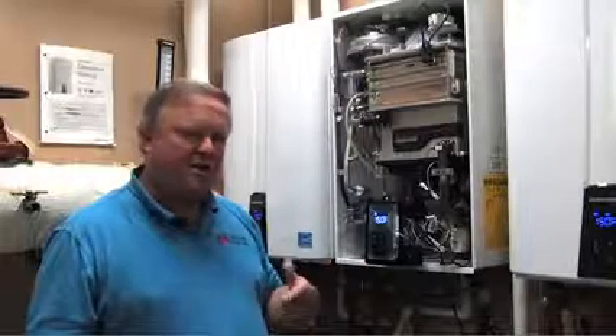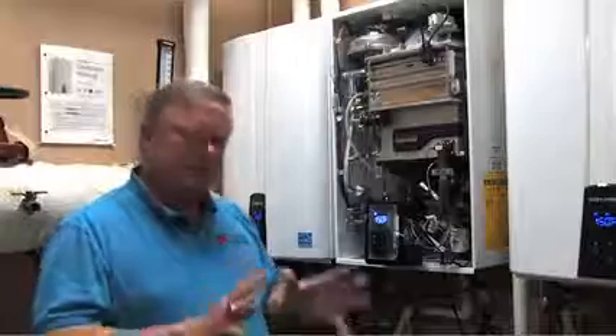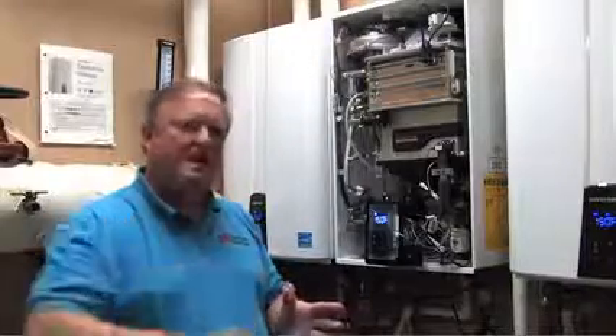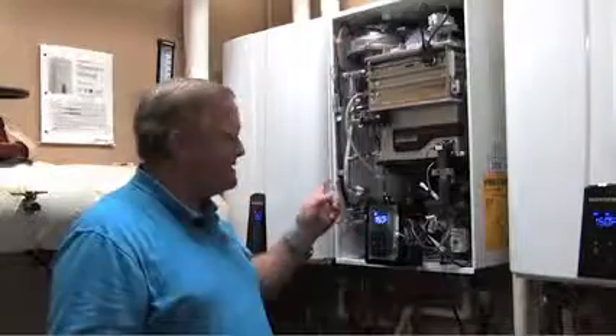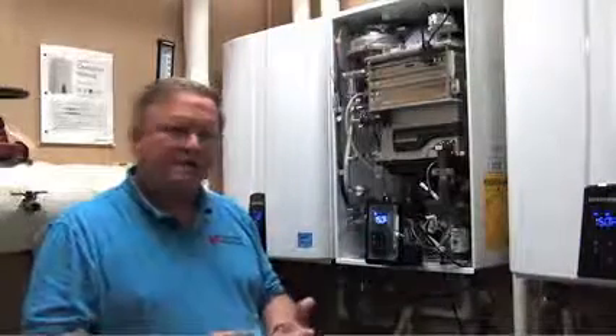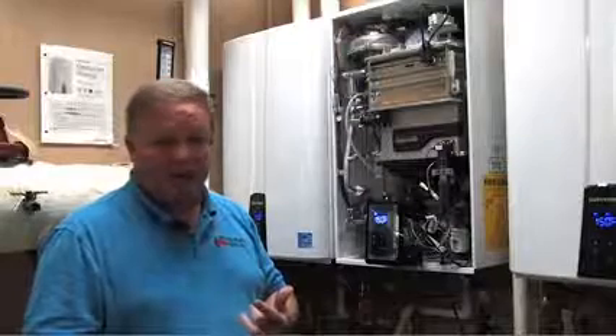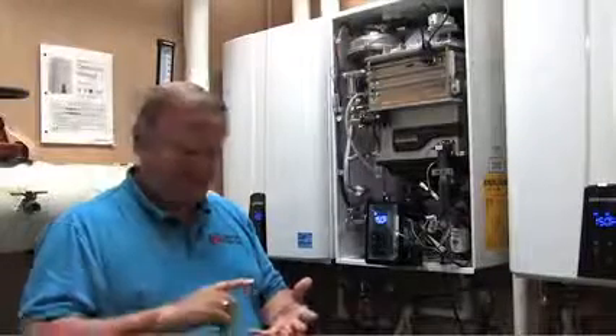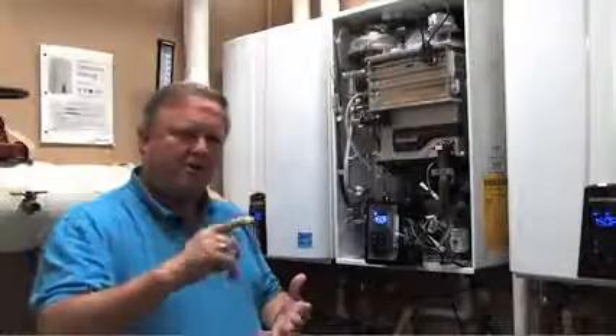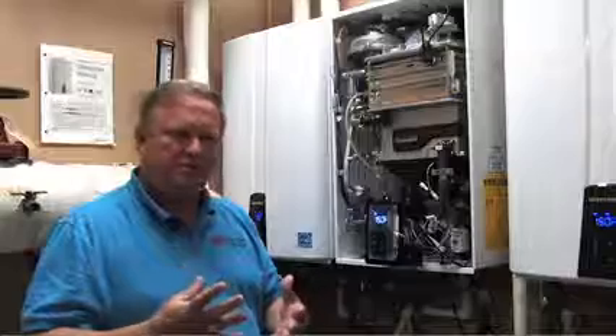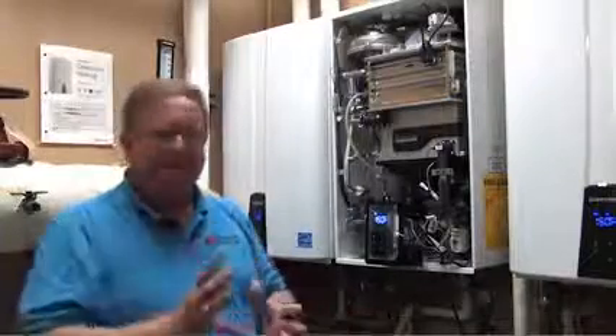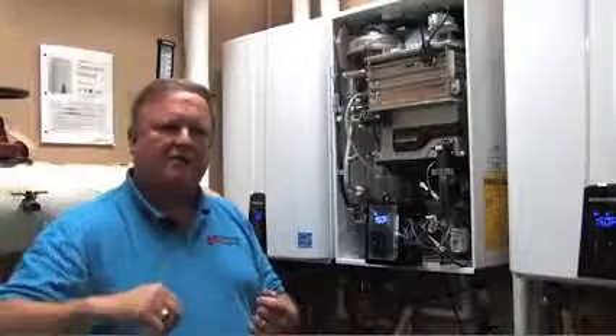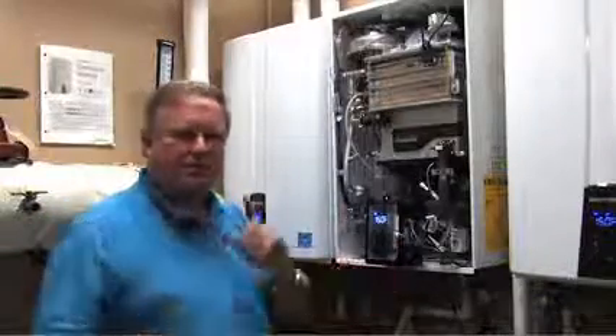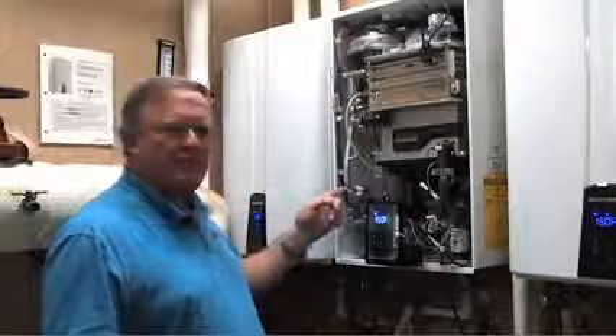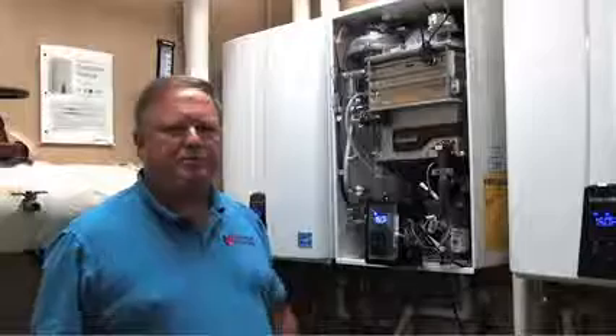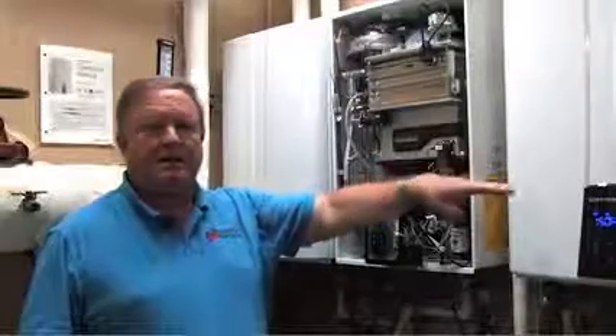Another important feature, because we're in a restaurant, picture a faucet that's being turned off multiple times. With any other product that doesn't have that buffer tank, what happens is they get a phenomenon called the cold water sandwich. And what that is, when the unit fires, it allows a little bit of cold water to come through first before it gets to full temperature. Any other manufacturers, not the Navien. And so picture if you're turning a faucet on and off, hot, cold, hot, cold, hot, cold. Not with the Navien. This buffer tank stores enough hot water that I can turn that faucet on and off multiple times and get consistent hot water. That's a very important feature.